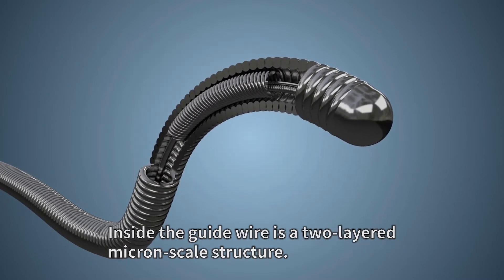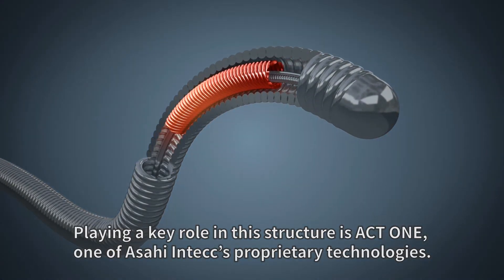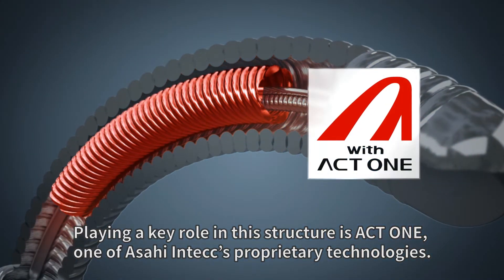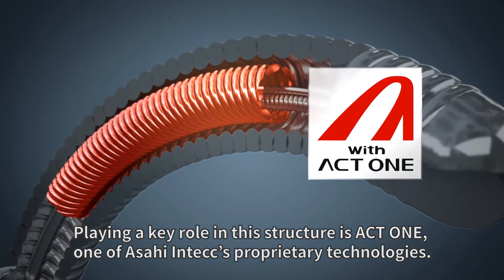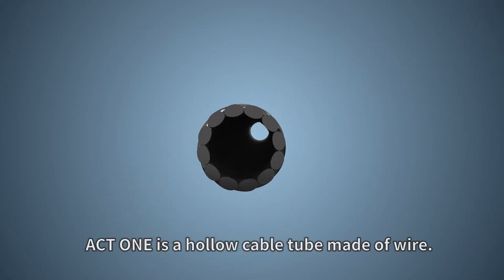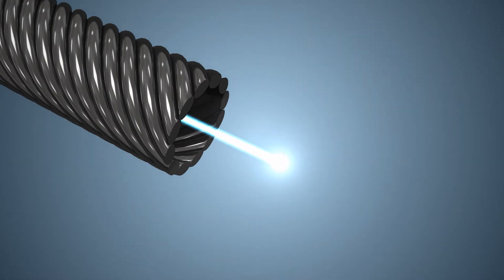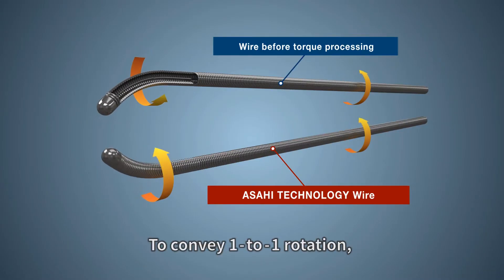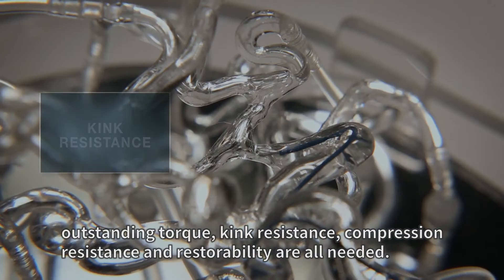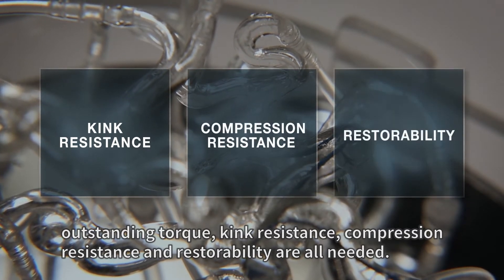Inside the guide wire is a two-layered micron-scale structure. Playing a key role in the structure is ACT-1, one of Asahi Intecc's proprietary technologies. ACT-1 is a hollow cable tube made of wire. To convey one-to-one rotation, outstanding torque, kink resistance, compression resistance, and restorability are all needed.